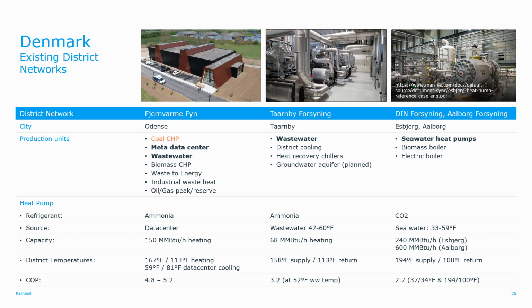And then on the right are two more cities. One is actually currently installed and operating - they have seawater heat pumps, very large units that are producing some pretty impressive heating temperatures and impressive COPs with very low seawater temperatures. I found out today they had some pretty cold temperatures this winter - I think they had a cutoff of 30 degrees Fahrenheit, since the water freezes around 29.5, so they deemed that very limited delta T provided small capacity. But it works down to 30 degrees Fahrenheit on the incoming seawater temperature, and they're able to supply 194 degree temperature to the network.